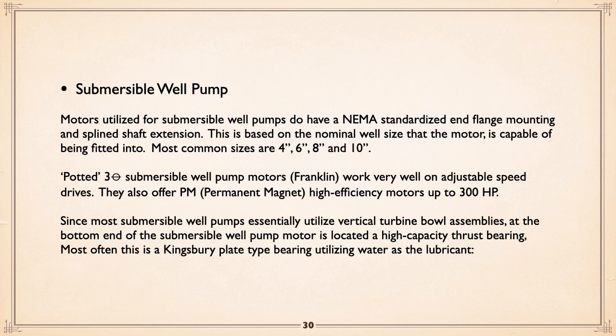One thing Franklin does with their submersible motors, they're potted. In other words, there's a combination of sand and silica that go into them. So they're actually potted, which is a good thing. A conventional motor on a variable speed drive, you will get sort of a halo current, which is not fatal but doesn't help the motor. Let's put it that way. It's there and you just live with it. Potted, that disappears completely. And Franklin has just come out with permanent magnet high efficiency motors up to 300 horse.